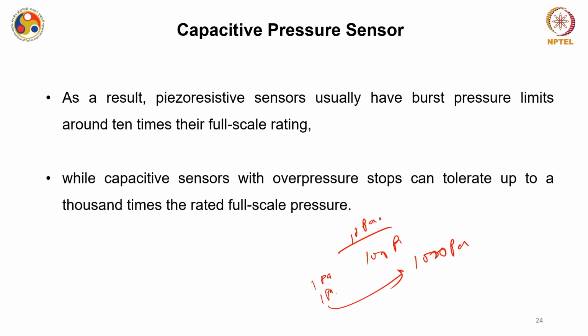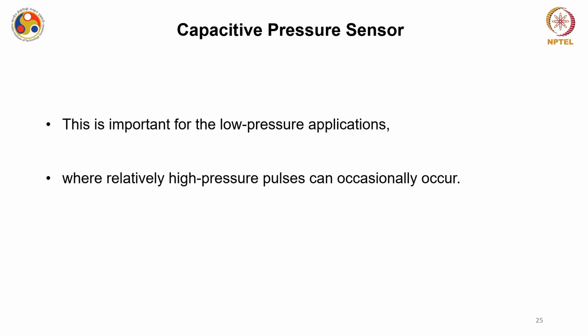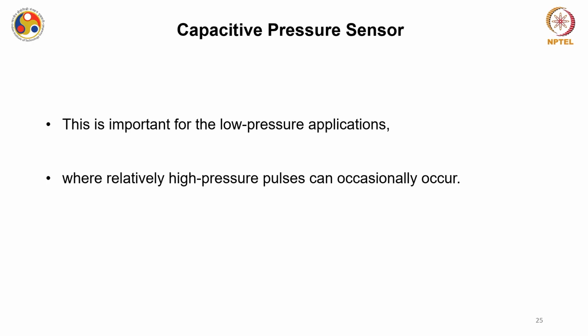However, this kind of capacitive sensor can withstand overpressure, and this is very, very crucial when you are dealing with micro pressure sensors and nano pressure sensors. Even in blood vessels, for medical devices particularly, it becomes very important, because you do not know the nature of the fluid you are measuring. It is quite possible that in low pressure applications you may have a relatively higher pressure pulse which can occur occasionally, and in those cases this capacitive sensor becomes very important.